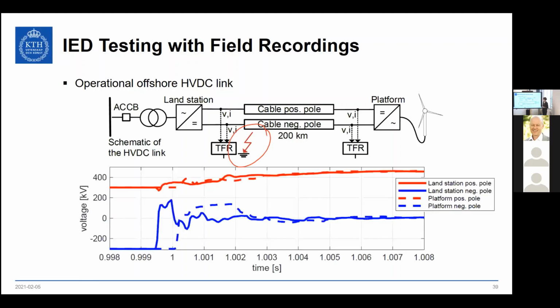Here you can see the fault recording from the actual link in the field. You can see how the negative pole voltage really nicely collapses, very clean. Then the same happens half a millisecond later at the platform. That delay is simply due to the fact that the traveling wave has to travel through the 200-kilometer-long cable. On the positive pole, we can see the voltage increase, since this is a symmetric monopolar system.